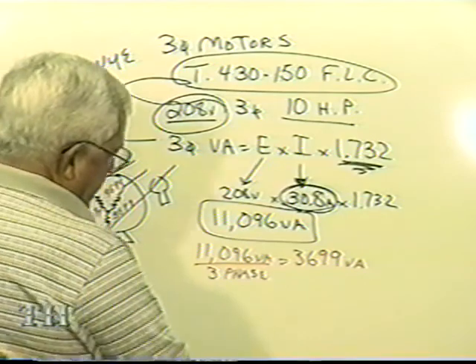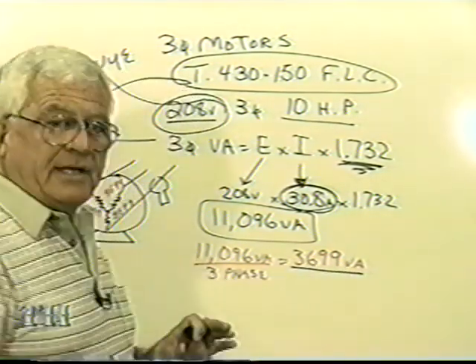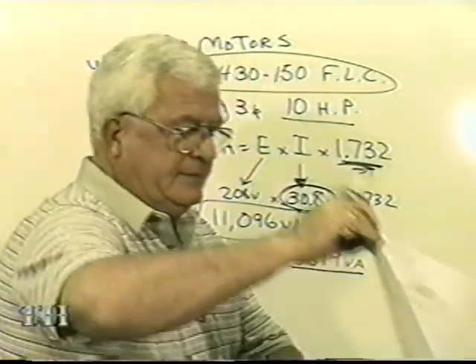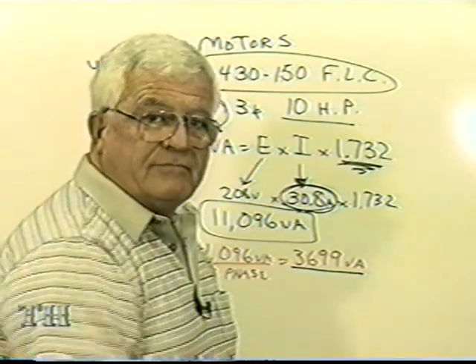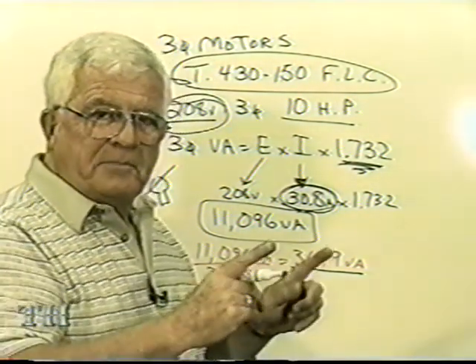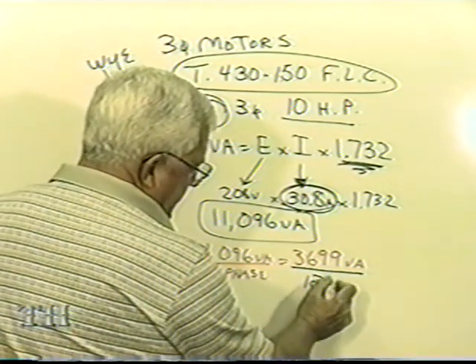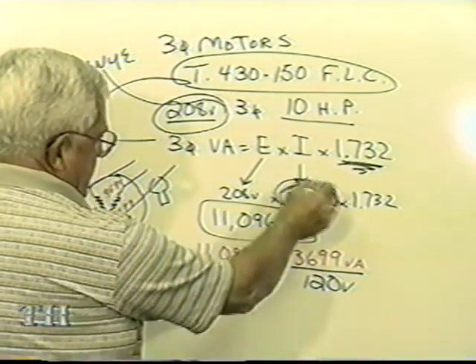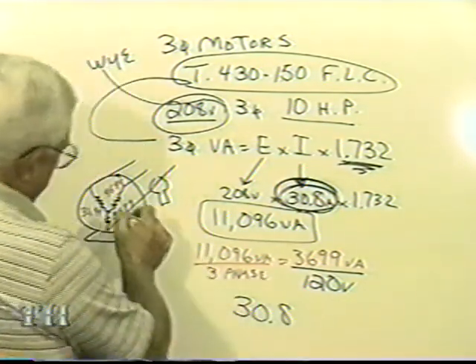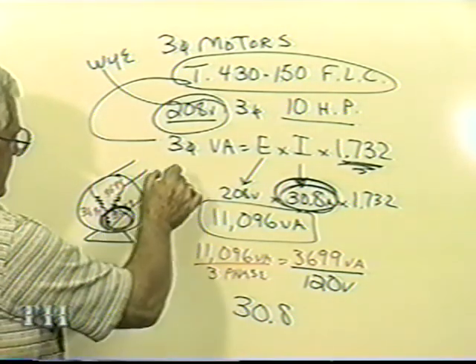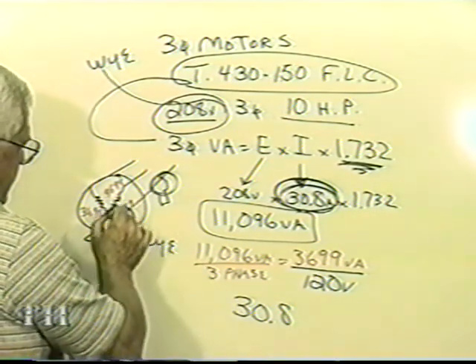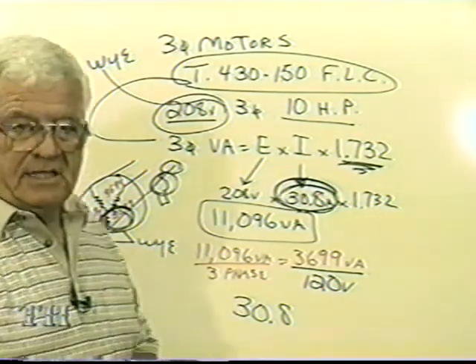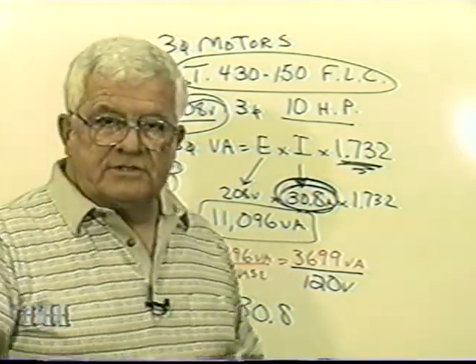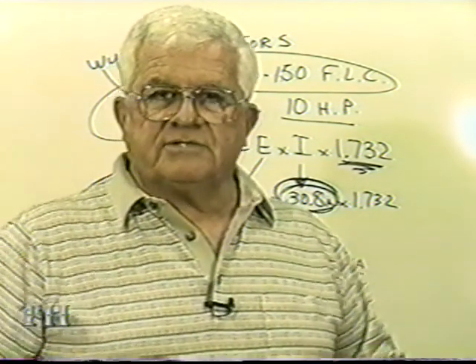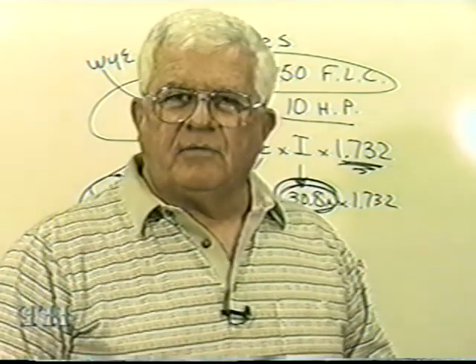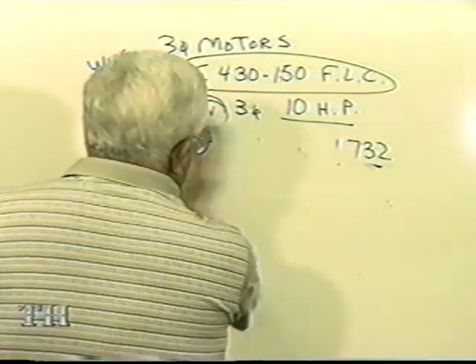Watch what happens. If you would take this number right here, and we said in our format, sheet 1, if we had 208 volts in the line, how many volts would we have in a phase? Remember our meter? 120. Well, if I took and divided this by 120 volt, guess what? 30.8. Right here. 30.8, 30.8. It's a Y. Coil phase amps is the same as line amps. So some of this stuff, even though it's a transformer, you can flip it right into a motor sketch and do something like that. I always say this on these, it's numbers. Once you have the format, once you learn it, you'll never forget it.